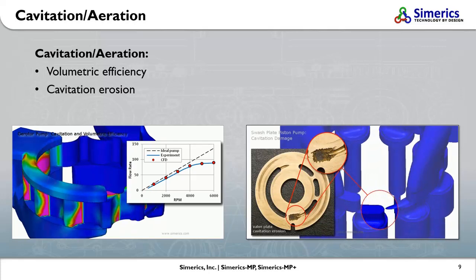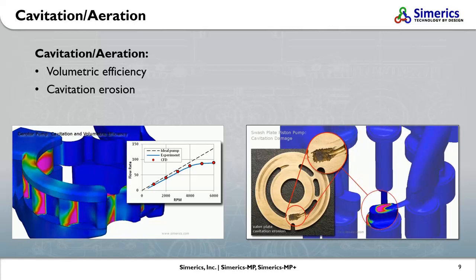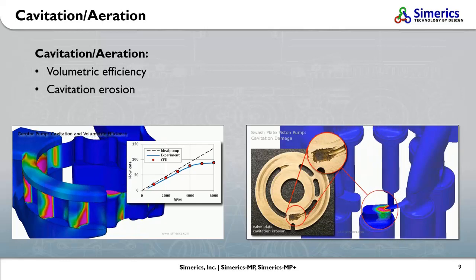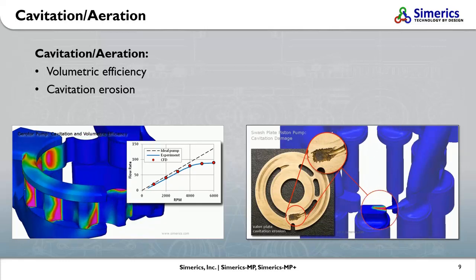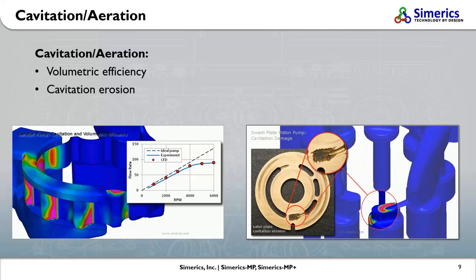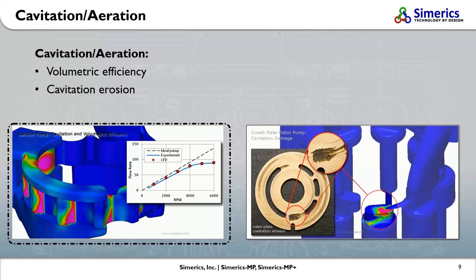In terms of cavitation, Simerics MP+ can perform two kinds of analyses. First, predicting the volumetric efficiency. For an ideal pump, the flow rate grows linearly with the pump rotation speed, as seen from the dashed line in the left diagram.